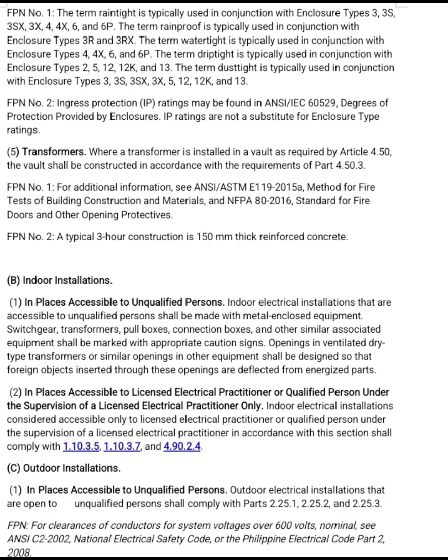Letter B. Indoor installation. Number 1. In places accessible to unqualified persons, indoor electrical installations that are accessible to unqualified persons shall be made with metal-enclosed equipment. Switchgear, transformers, pull boxes, connection boxes, and other similar associated equipment shall be marked with appropriate caution signs. Openings in ventilated dry type transformers or similar openings in other equipment shall be designed so that foreign objects inserted through these openings are deflected from energized parts.